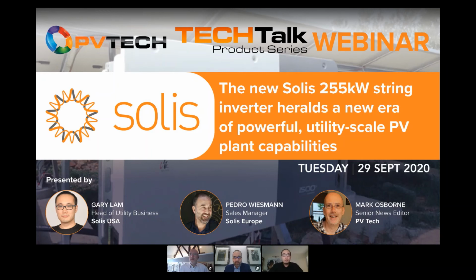But for us, if the Solis 255 is designed for use in a utility project, that basically means the whole site only has PV and nothing else. And our inverter outputs such a clean AC waveform that it does not include any noise on it. So the PLC signal can transmit within the site very nicely. And at the end, our large voltage transformer will act as a big LC filter and filter out this signal. So this is why we need to install a PLC CCO device before the transformer, to keep all the signal. And the signal will not go beyond your mid voltage or high voltage transformer.